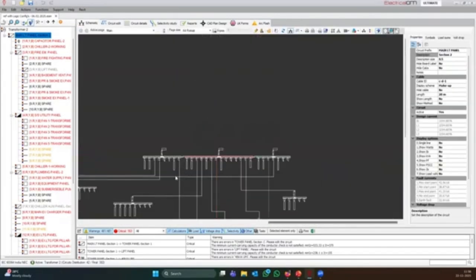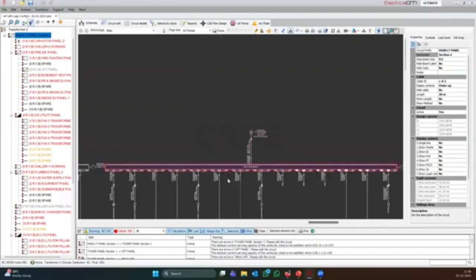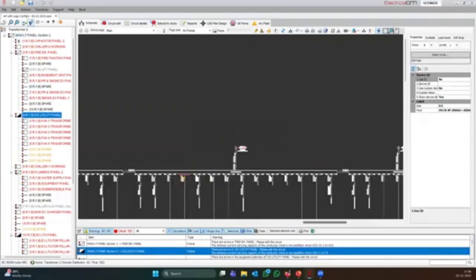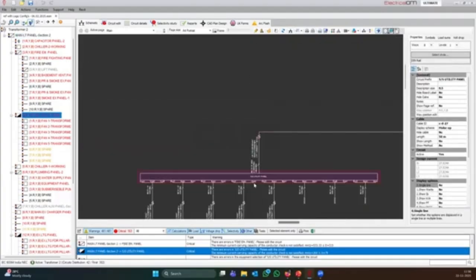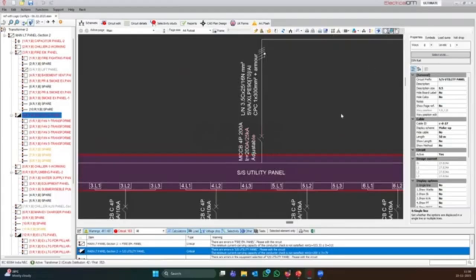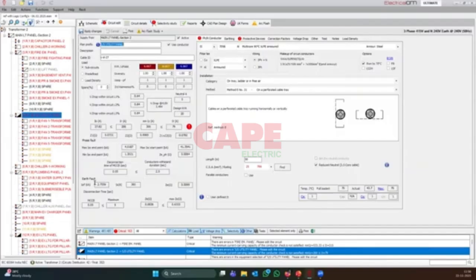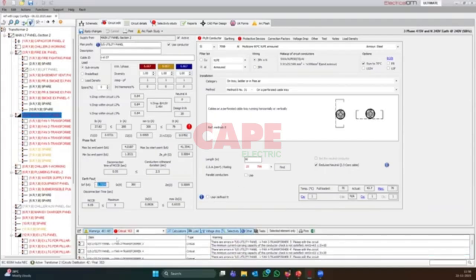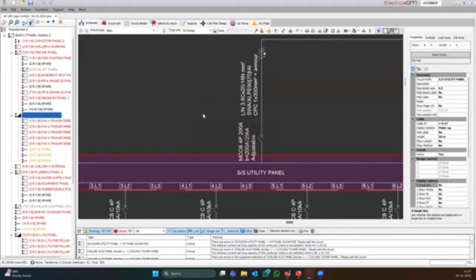But when you come just below it, downstream, if I take this utility panel, for example, the fault current at this location is going to be only 2.755 kiloamps. Obviously, there are some errors in it, something around 500 or 600 errors. Do ignore this because this is a project which we have got and we are doing some design verification. So the earth fault current is going to be very much lower. The earth fault current at this location is going to be 2.77 kiloamps, but at the main panel it is something close to 32 kiloamps.